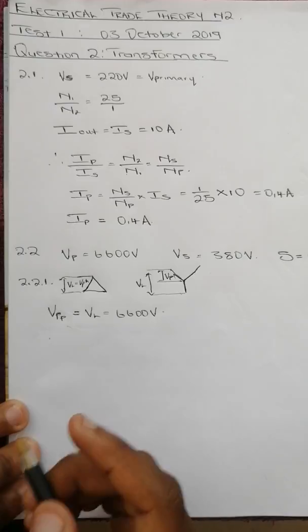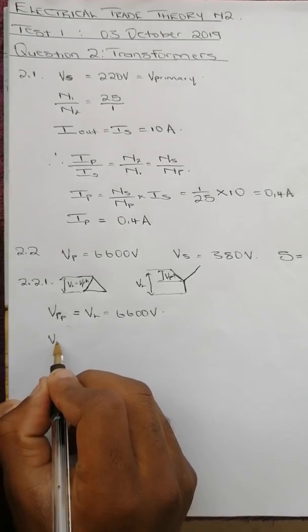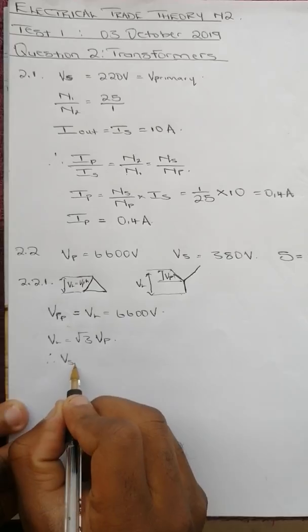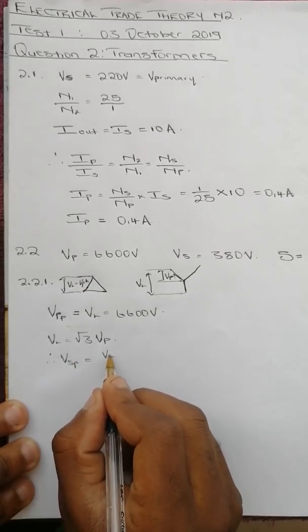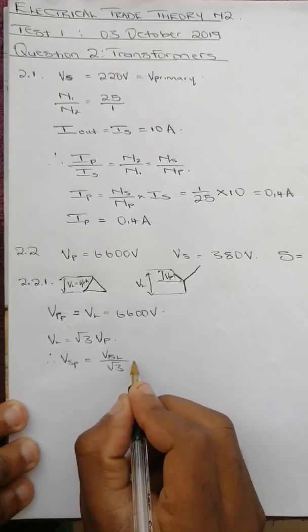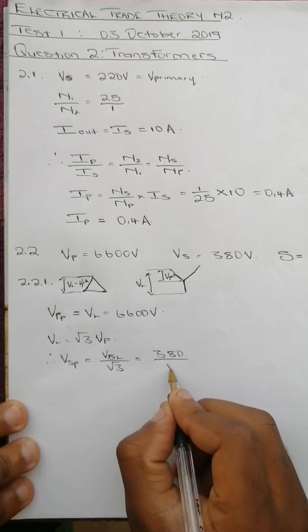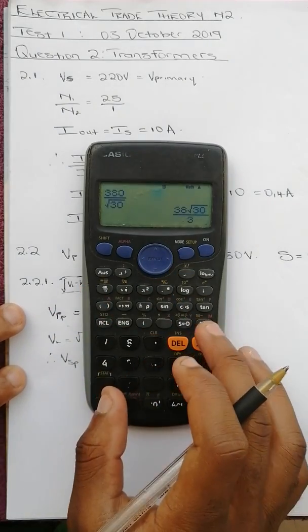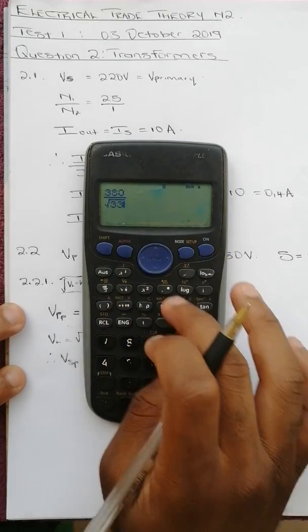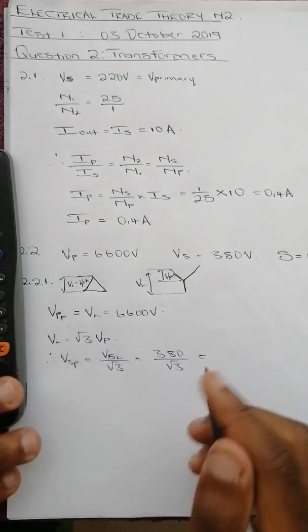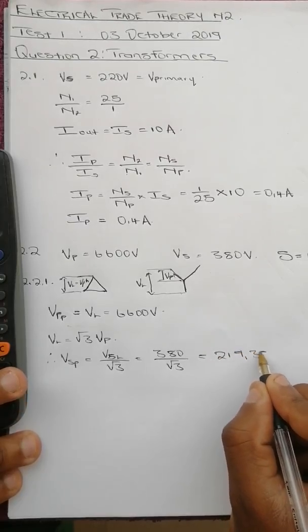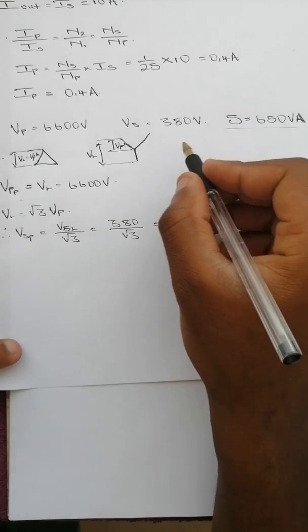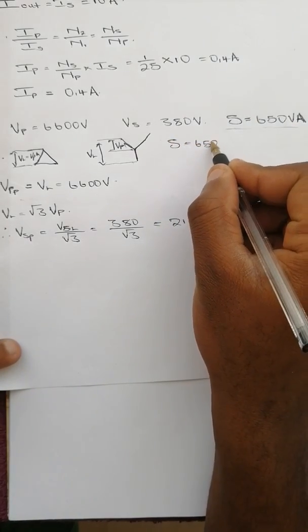For the star-connected secondary, V line equals square root of 3 times V phase. Therefore, the secondary phase voltage equals V line secondary divided by square root of 3, which is 380 divided by square root of 3, giving us 219.39 volts. S equals 650 volt-amps.